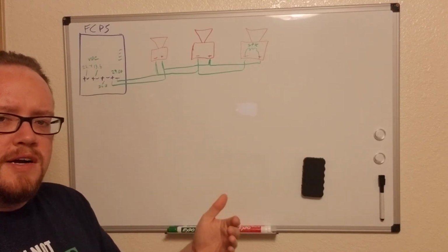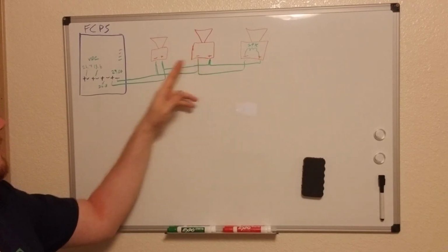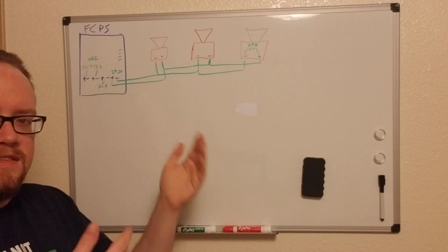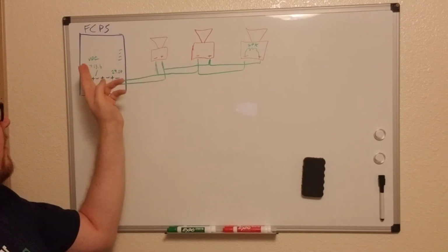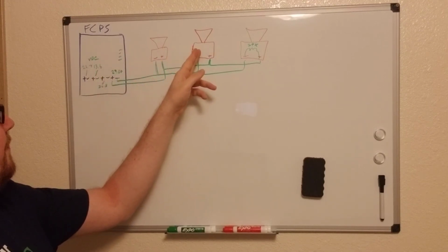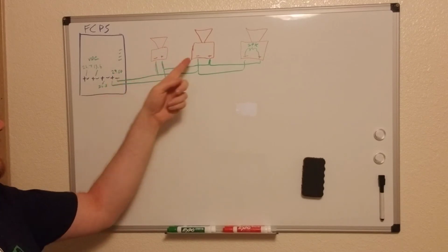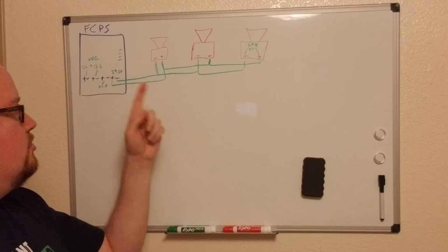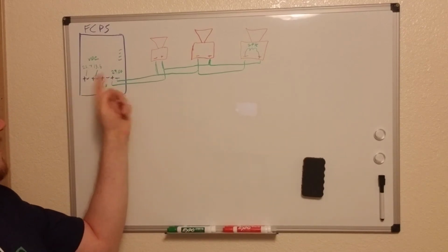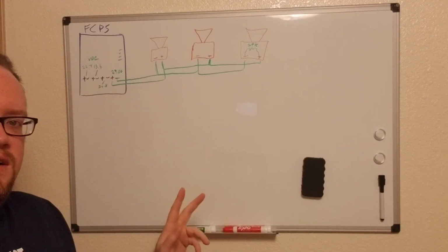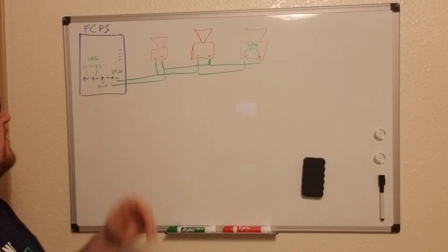It's still a part of the process to make sure the circuit's good going that direction, and then you check voltage going the other way and see if it's within the range that you want. Like if you pull these wires off between the head end and this strobe, and instead of seeing the 29 volts, because as soon as you lift the wires off, now it's an open circuit, so you should see a higher voltage. But if you still don't see the kind of voltage you want, okay, the problem's still back closer to the panel. It's not that direction, it's more this direction.